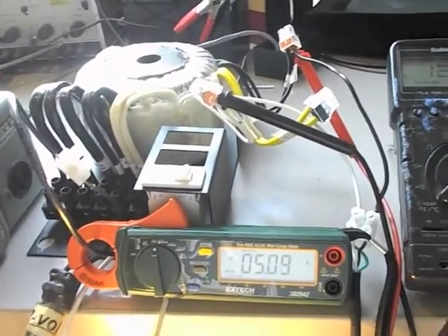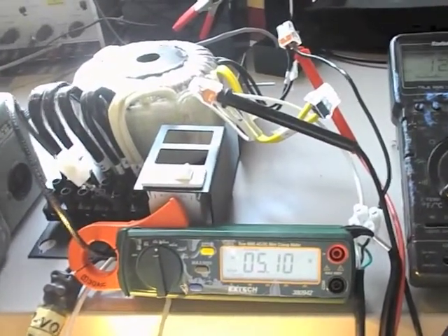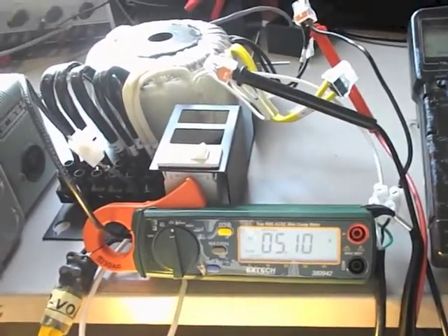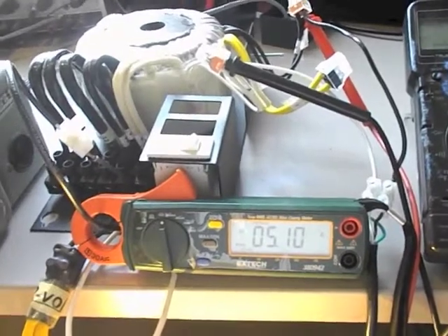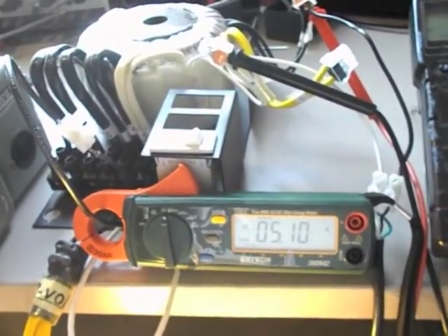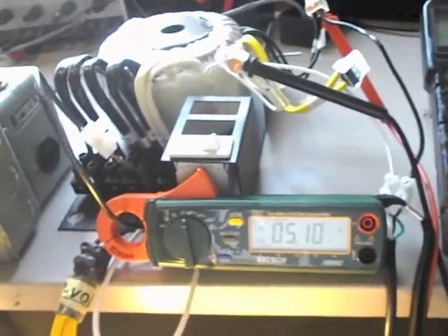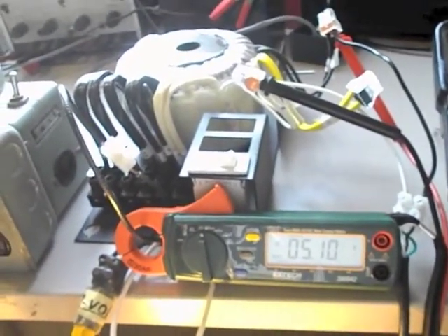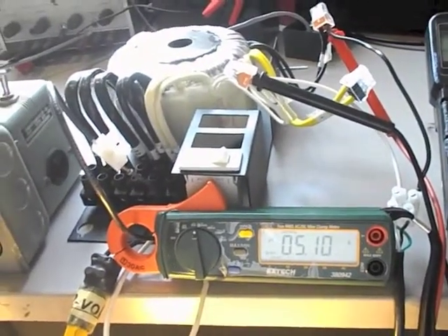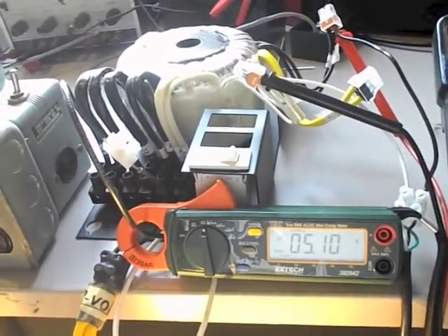So this is the risk that you run if you size the breaker to handle 100% load. The day you installed this, perhaps it did not exceed the load, but the conditions the day you made the installation may not be the same conditions a year later or a week later.